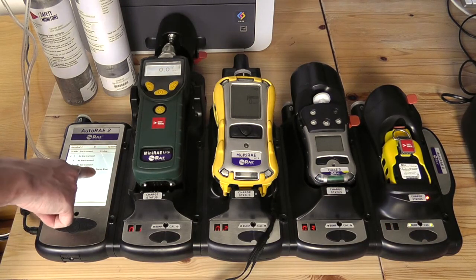In this case, while we're sorting out the rest of the setup, we'll perform a bump test on the ToxiRAE Pro, and it's letting us know that a bump test has been requested on that device. To get the MiniRAE into communications mode, please scroll across until we get to 'enter AutoRAE 2 and stop measurement'.